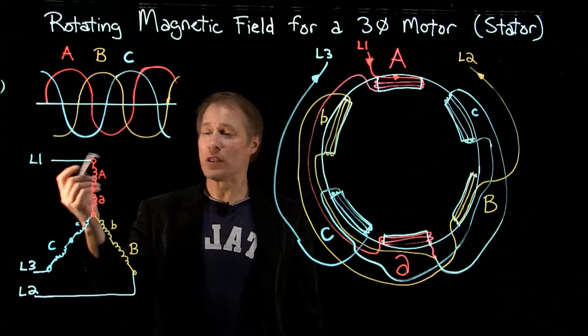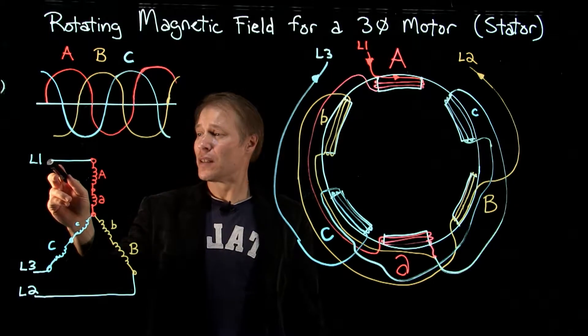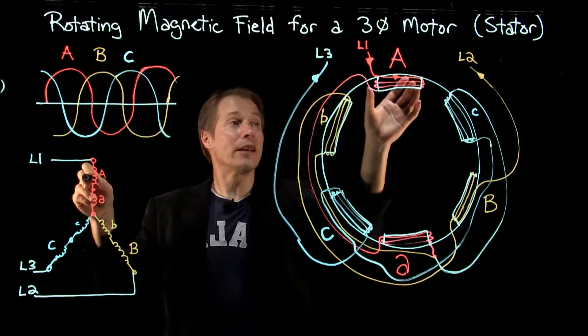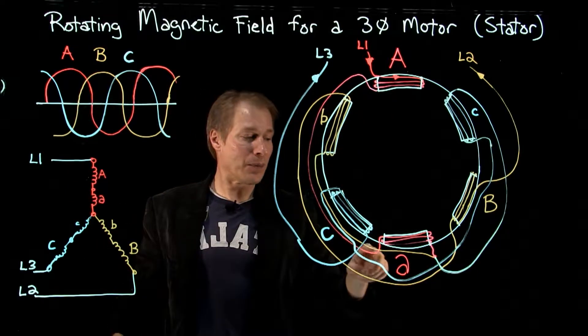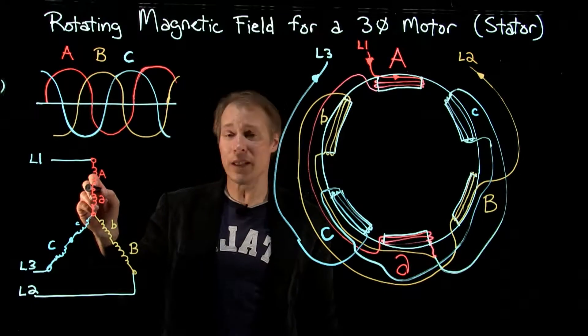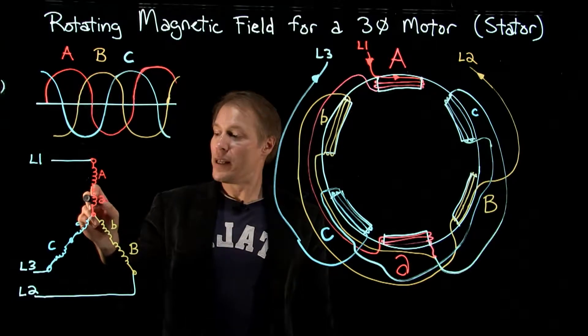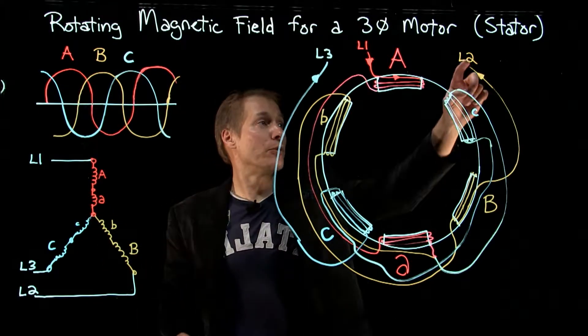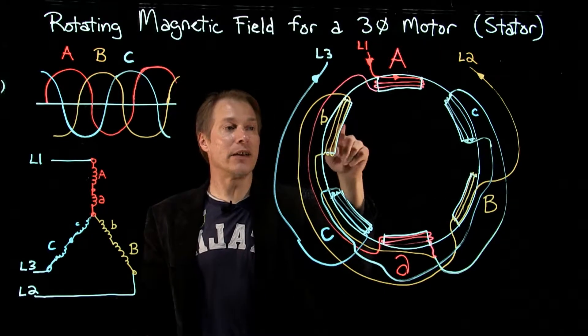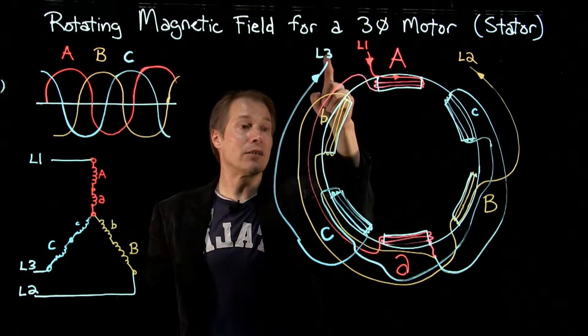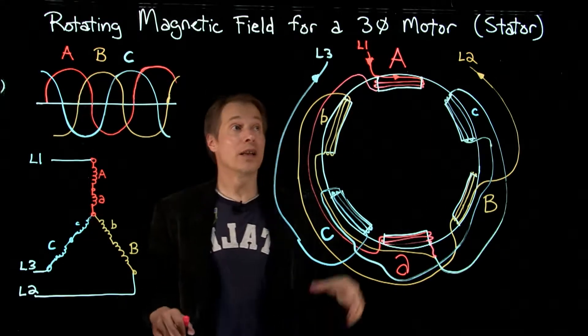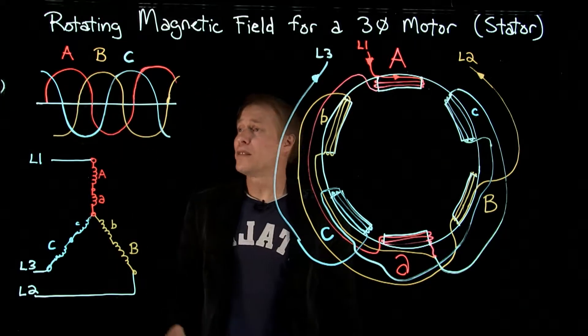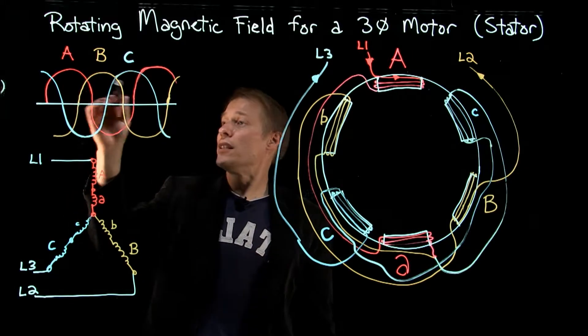So we have L1, which is also the red phase or the A phase. L1 connects to the A coil. In the diagram, L1 connects to the main pole or main coil, with a wire wrapping around connecting it to the secondary coil — shown in the schematic through this point, then to the secondary A coil. Similarly, L2 goes to the B main pole and then to the secondary. L3 goes to the C main and then secondary. The main poles are 120 degrees apart in this motor, and the sine waves are also 120 degrees apart.